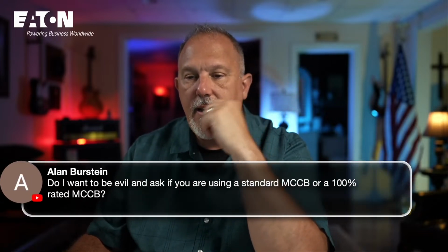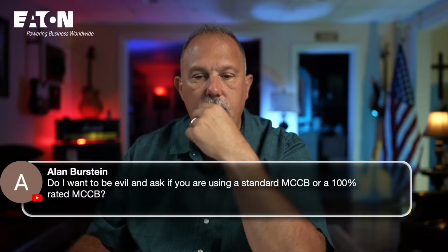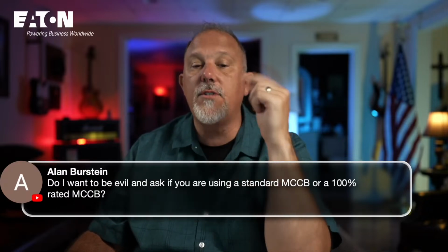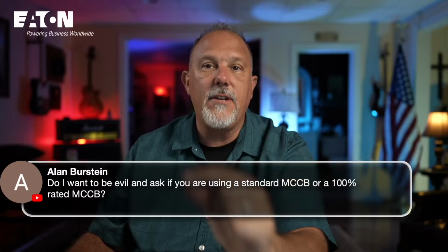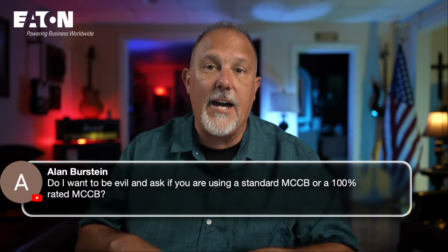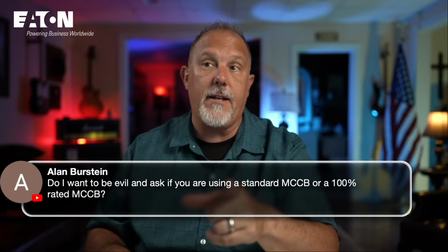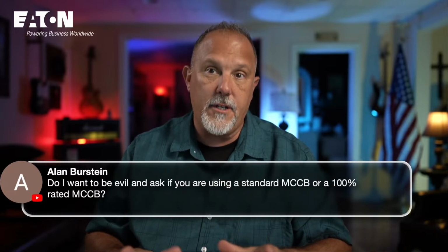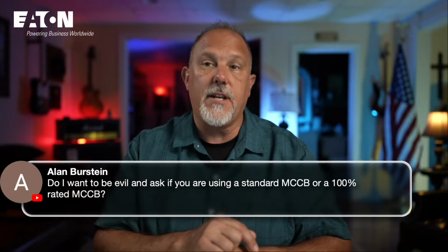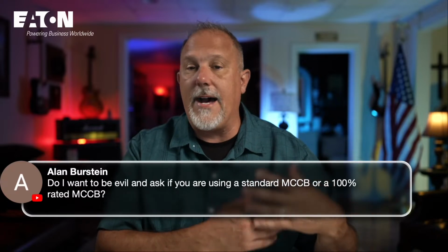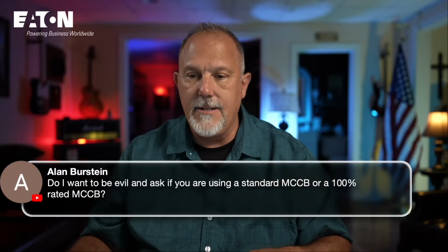Do I want to be evil? Oh, and ask if you are using a standard 80% rated. If I was at 100% rated equipment, because remember, Alan, it's not just the breaker that matters. The equipment also matters. I might need a panel board with a high density copper, all that jazz. All right, yes, I'm being evil.